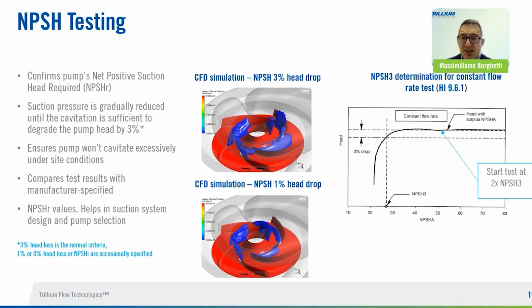How is this test generally conducted in the test room? Basically, the industry standard is to run at constant flow rate. Let's say in the slide there is a picture from HI 9.6.1. Generally, this test starts at 2 times the NPSH required, and basically you decrease the suction pressure until the cavitation is enough to degrade the pump head by 3%. So it is the 3% drop. Okay, we can move to the next one.